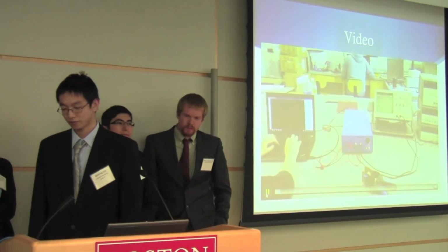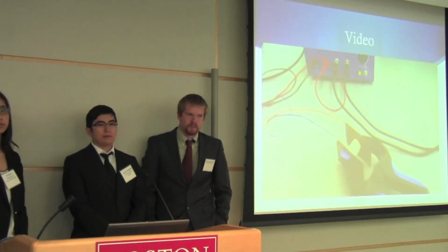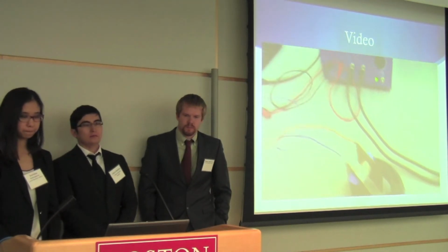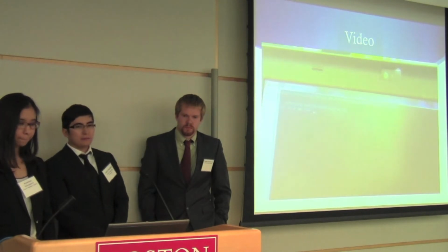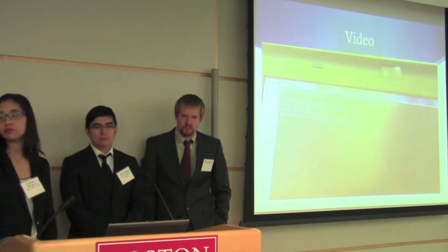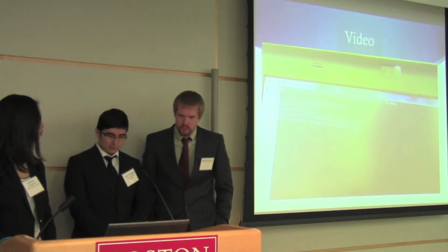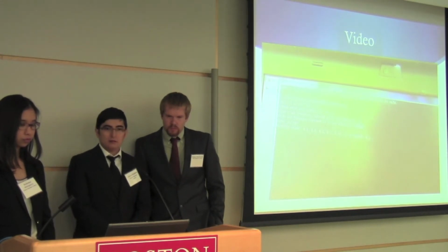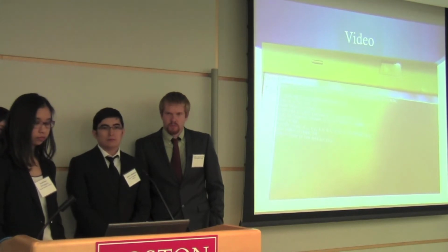Here's our full analyzing setup using a computer interface and an oscilloscope to monitor voltages. We're using a cement sample donated from Schlumberger-Doll. The user now has to enter a set of parameters for the test. We are selecting a frequency sweep of 25 Hz to 200 kHz. The output voltage is going to be 0.3 volts RMS. The number of steps 250. And now the user is prompted for the file name in order to save the text file.